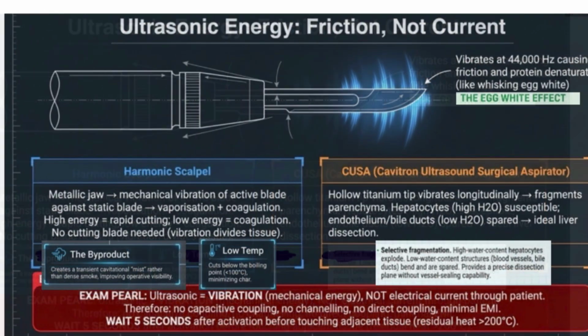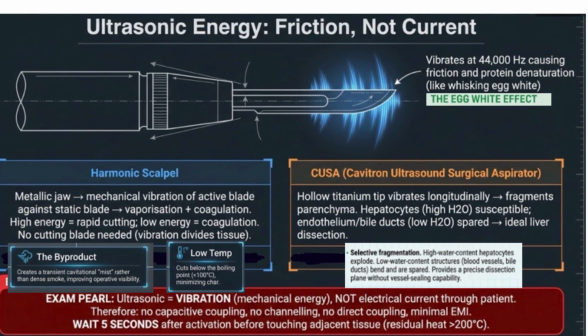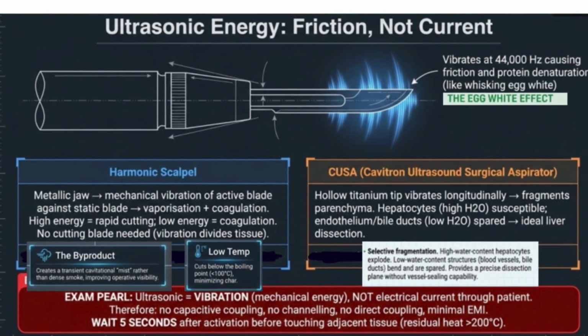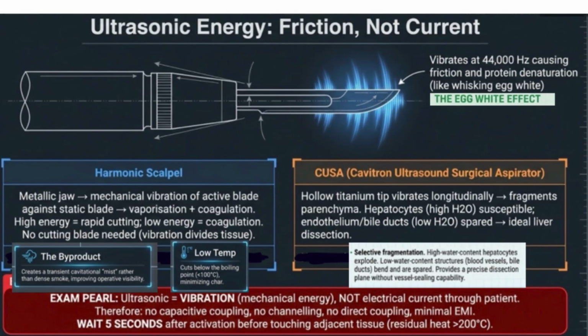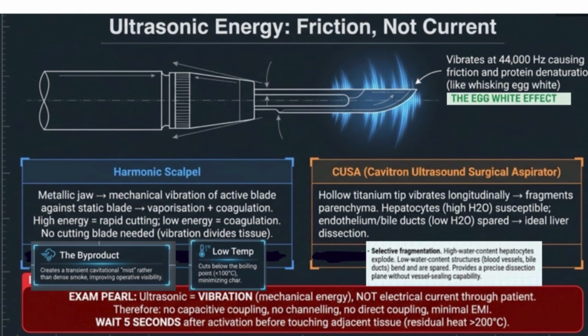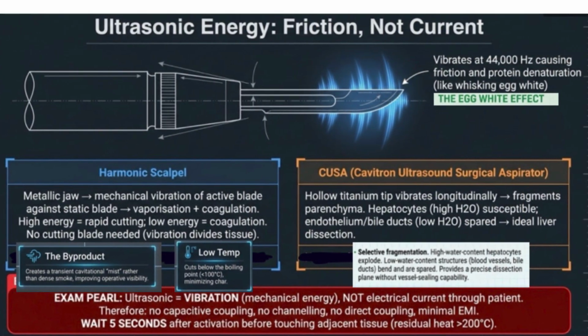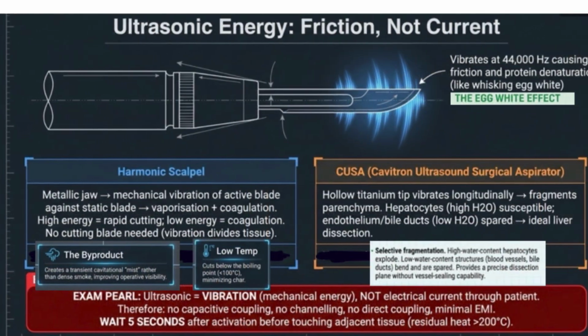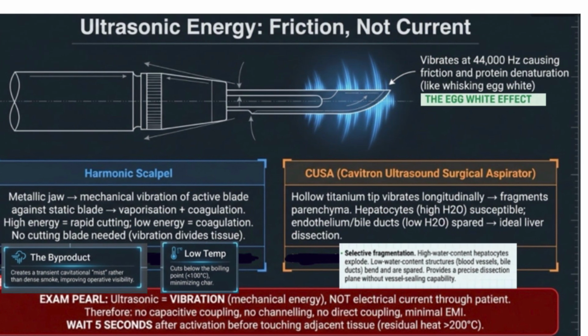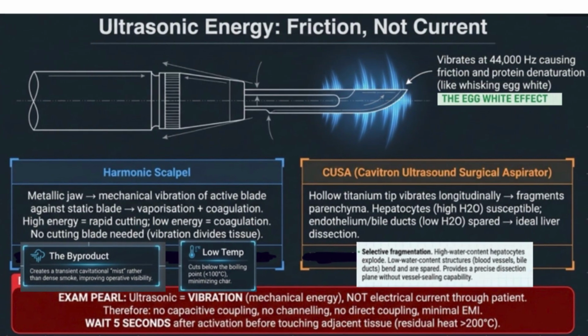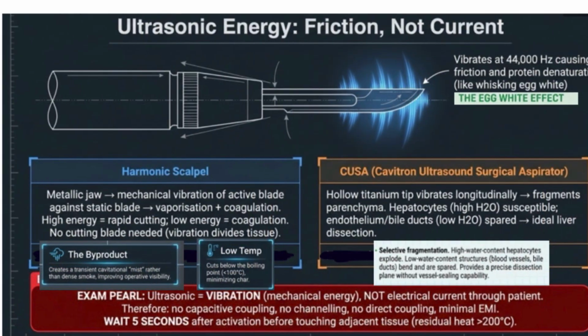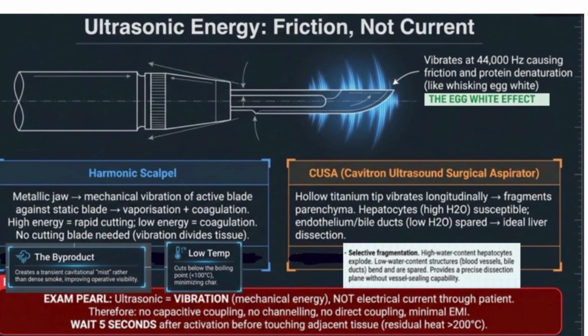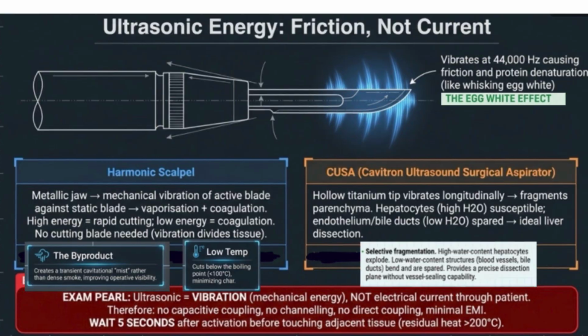The byproduct creates a transient cavitational mist rather than dense smoke, improving operational visibility. It works at low temperature. It cuts below the boiling point, that is less than 100 degrees, and minimizes the charring. In CUSA, the Cavitron ultrasonic surgical aspirator, the hollow titanium tip vibrates longitudinally and fragments the parenchyma. The low water content endothelium and bile ducts of the vessels are all spared, while the high water content hepatocytes are exploded. This provides a precise resection plane without vessel sealing capability.